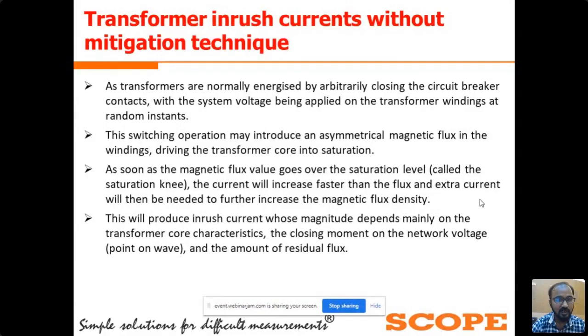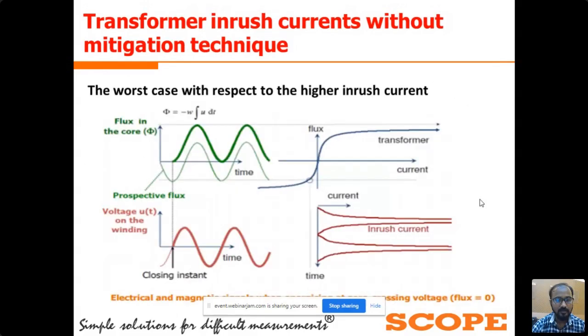So if transformers are normally energized by arbitrarily closing the circuit breaker contacts, with the system voltage being applied on the power transformer windings at a random instant, and if we consider a random instant and we de-energize the power transformer, we don't know at what electrical angle the CB contacts will open and what the magnetic flux available in the transformer core is. So to avoid that, we are using the control switching device. As we discussed, these are the target points that we are using to close and open the CB for the control switching of the power transformer.